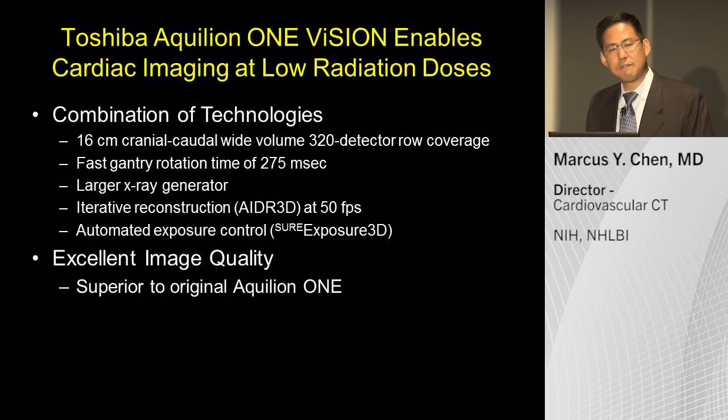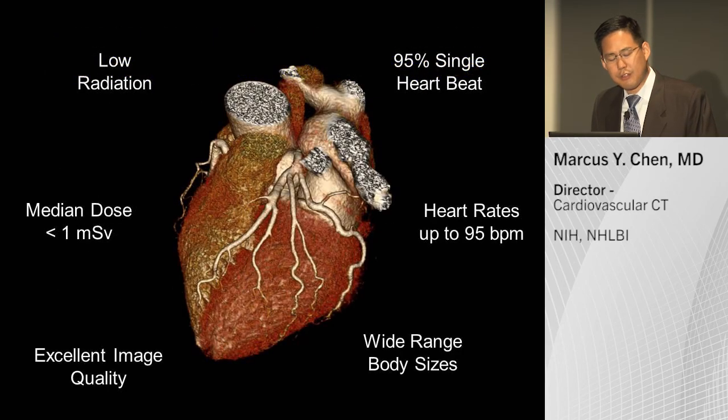Overall, the Toshiba Aquilion ONE ViSION platform enables cardiac imaging at very low radiation doses. This is due to a combination of technologies: the wide volume 320-detector system, the fast gantry rotation time of 275 milliseconds, the larger X-ray generator enabling more imaging at 100 kV, iterative reconstruction with recons at 50 frames per second, and automatic exposure control. Our median dose is less than one millisievert, 95% of scans are done in a single heartbeat, we've scanned heart rates up to 95 over a wide range of body sizes, and we have had excellent image quality overall.